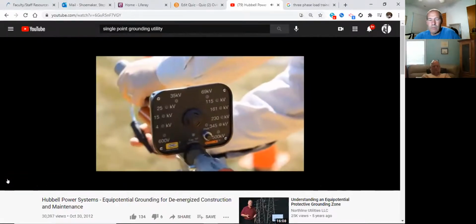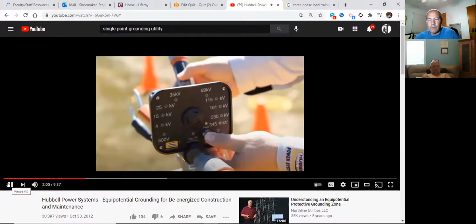But first, he checks an auto-ranging voltage indicator for operable condition. So this is a Chance video, and this is a Chance voltage tester. So I'm sure they're here and they're advertising some of their stuff. What are some of the ones that we talked about before as far as testing our primary? What can we use? The phasing sticks? You can use phasing sticks to get an indication of voltage that's present on the line. They only go up to the hundreds. What else do we use? It was that little small black thing that we can put on the end of the stick.